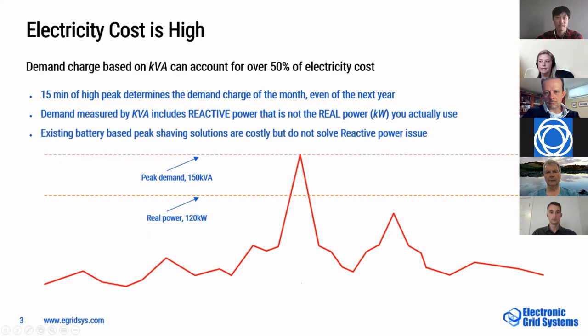The problem we are trying to solve is the high power demand from buildings. This is a painful problem for many building owners because over half of the electricity cost is typically spent on demand charge. The demand charge is based on the maximum power you use in any day of the month, so 15 minutes of high power demand will determine the demand charge of the whole month, and even the next year, even though you have very little power use the rest of the time.